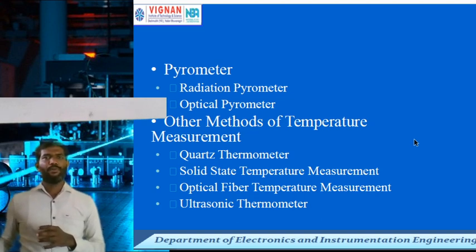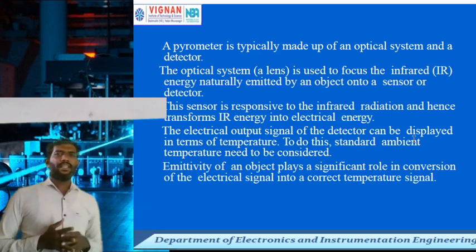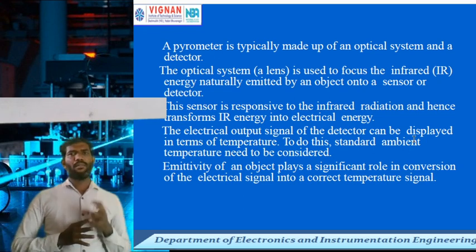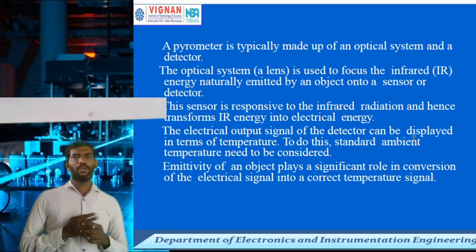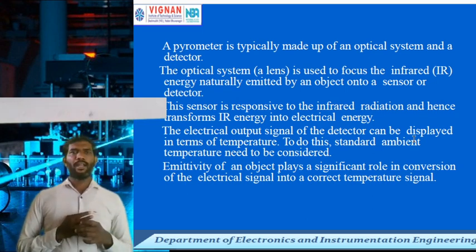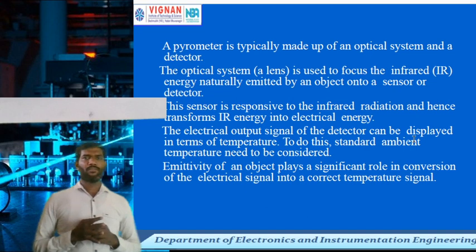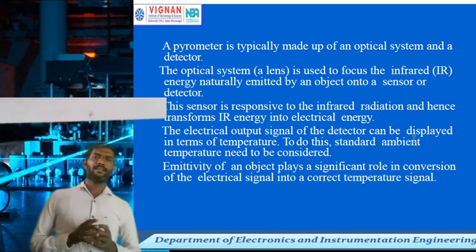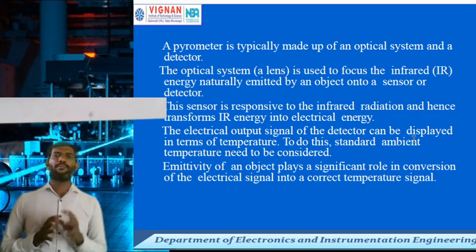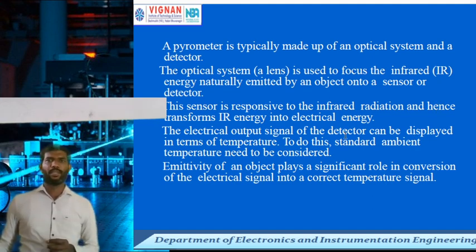Let us see the types of optical pyrometer and radiation pyrometer. A pyrometer has different internal parts — the optical system and detector are very important. The lens system, called the optical system, is used to focus the infrared energy naturally emitted by the object onto the sensor or detector. The sensor responds to infrared radiation, and that IR radiation energy is converted into electrical energy. The electrical output signal of the detector is then displayed in terms of temperature.